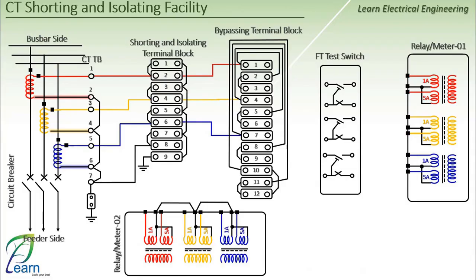Bypassing TB is used in the case where I have 2 protection relays or 2 metering devices connected in series on the same CT secondary, like when you have the overcurrent and breaker failure as 2 separate relays connected in series, or for example, when you have the BCU, which is the Bay Control Unit, and the DSM, which is the Dynamic System Monitoring, connected in series.